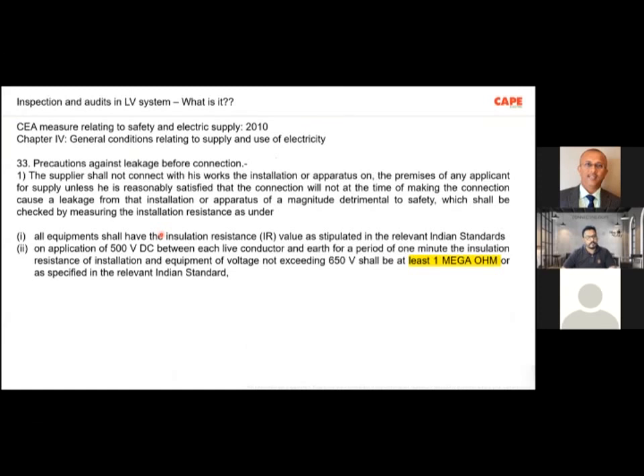Now, what kind of inspection is required as per the regulation? Please understand, the Government of India, Central Electricity Authority has the regulation, CEA measures relating to safety and electric supply. Regulation 33 talks about the protection against leakage, and here sub-regulation number 2 says every electrical installation not exceeding 650 volt shall be at least 1 mega ohm. What is this? This is nothing but the insulation resistance testing, to ensure that the appliances, connected devices and the electrical wiring are not creating any leakage. This is a mandatory testing.